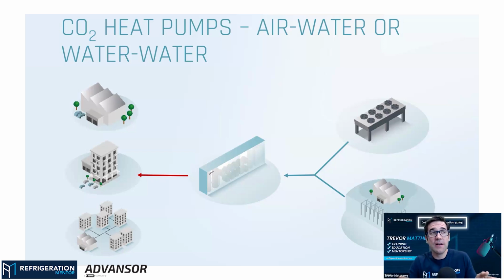And that one there is the basic and number one thing that you need to check. But I've talked to so many manufacturers out there where that's hanging off. It's not insulated. It's the wrong sensor, like they're using a CPC sensor for a Danfoss controller or vice versa, like a PT1000. This is what caused the issue, and that's in all their checklists. I've read a lot of CO2 manuals, and that's one of the biggest things. It's always highlighted and always in the manual: you've got to make sure that's landed properly. So thanks for sharing that.